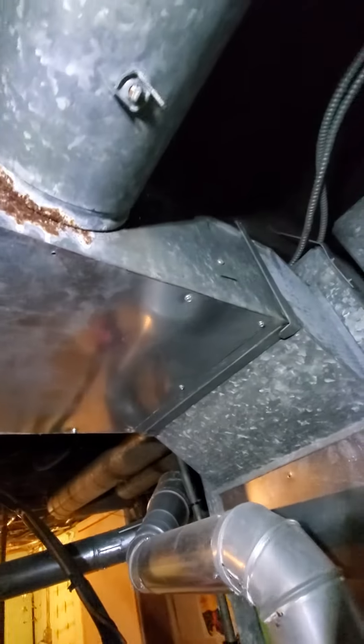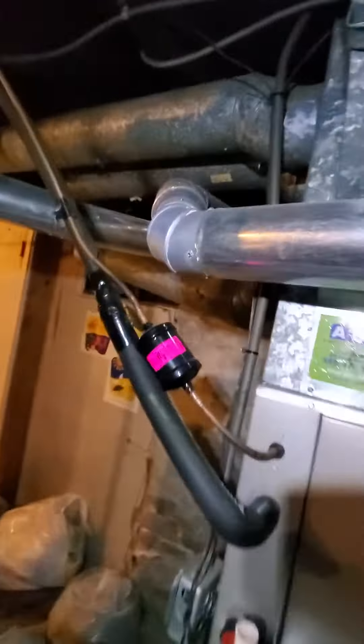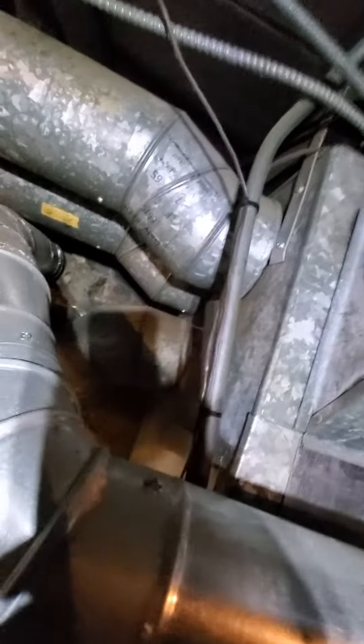So you can kind of see the evaporator coil, and then your supply. You have a supply trunk here at about 16x8, and then I'm counting about four 6-inch rounds. You can kind of see about three here, and there's one on the back end as well.